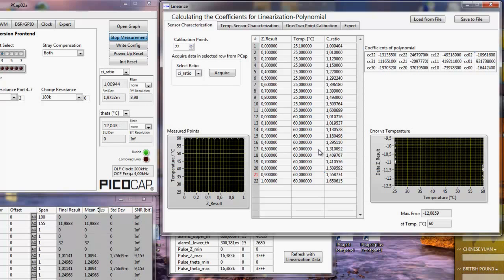And of course the parameter settings and the linearization always work in conjunction with the firmware. Now in the beginning, when I started the project, the firmware was already downloaded in the background by loading the project. For a sensor to have the firmware permanently, of course the firmware must be downloaded to the OTP. I will just demonstrate how this works without doing it, because the OTP can only be programmed once, of course.